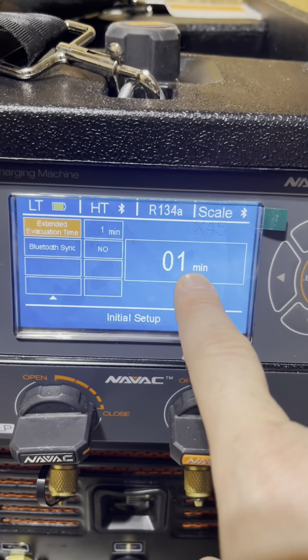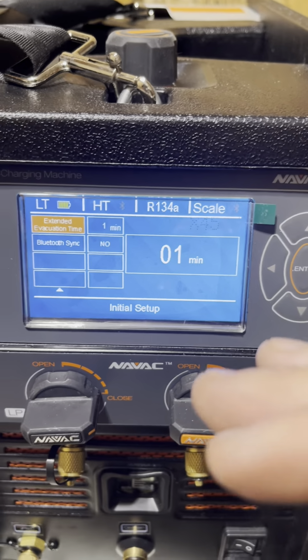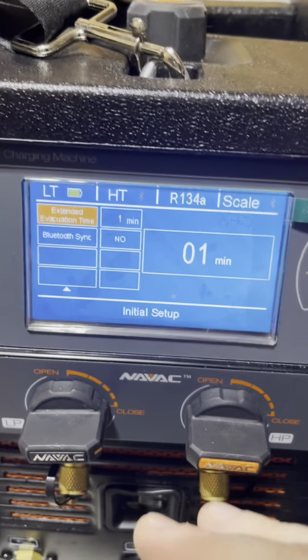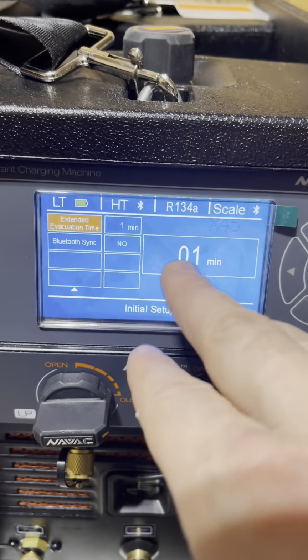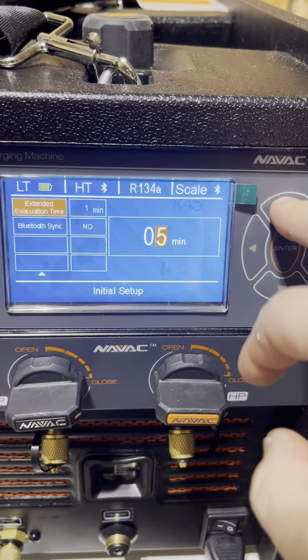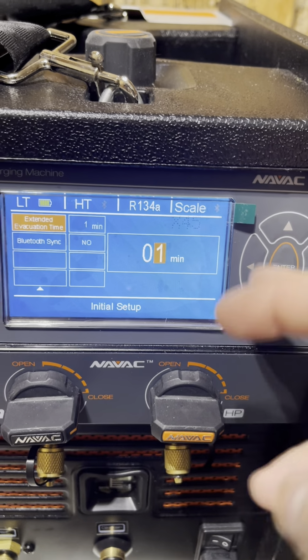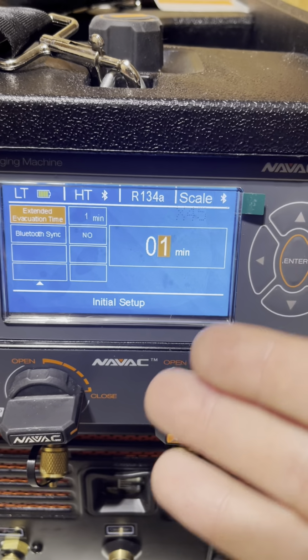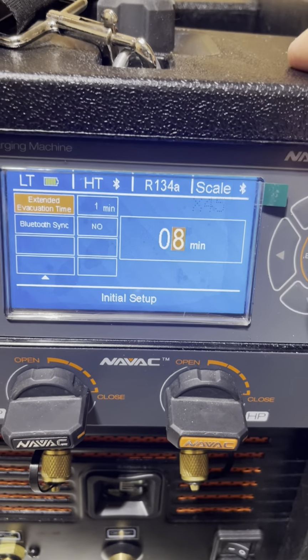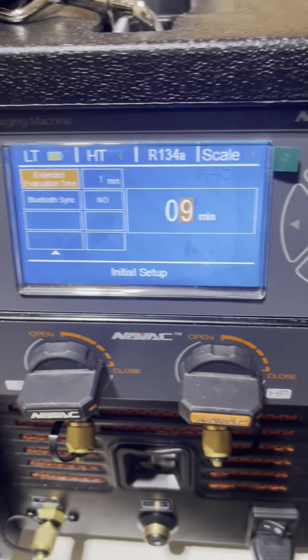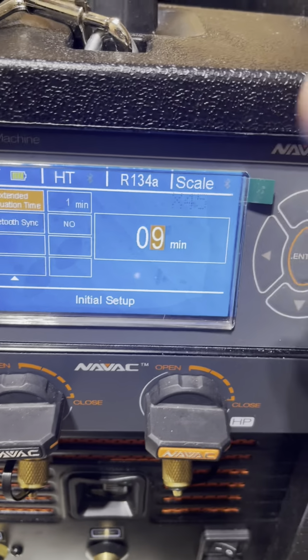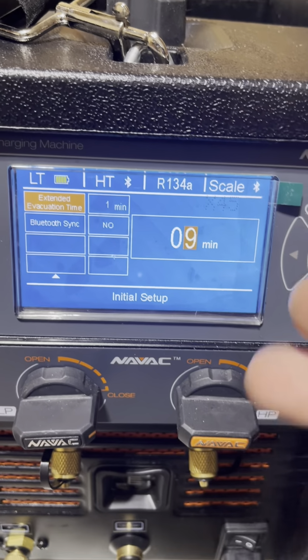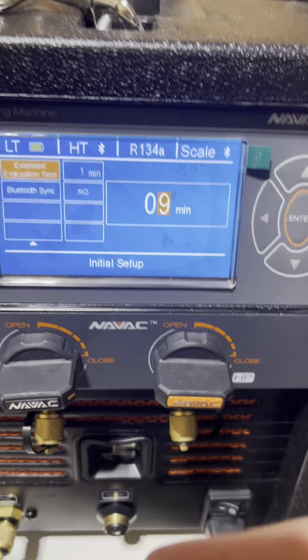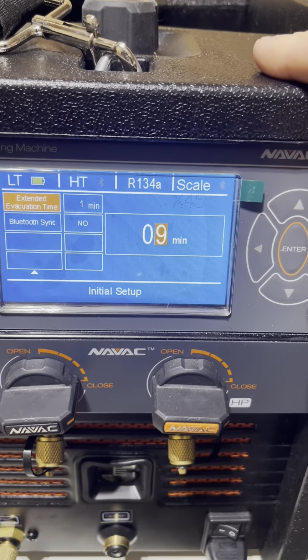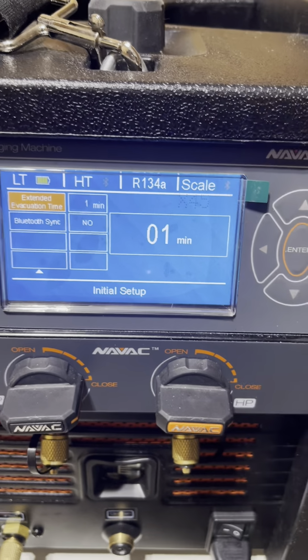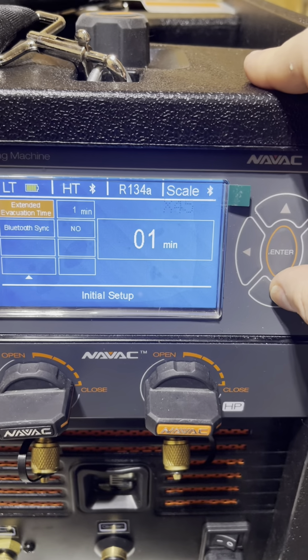Extended vacuum time, I did it for 1 minute. What it is that once it reaches the right micron level, it will pull for another minute before it goes to the next stage. You can play around with that, up to, I think, 9 minutes. That's the maximum. I did it for 1 minute. If you really want to make sure you pull a really good vacuum on your system, you can do 9 minutes and it will pull the vacuum below the desired micron that you set up in the system. So if your desired micron was 500, it will pull below 500 for the next 9 minutes, even if the desired vacuum was reached. I like to do it for 1 minute, but again, it's your own preference. You can play around with it. You can do whatever you like.